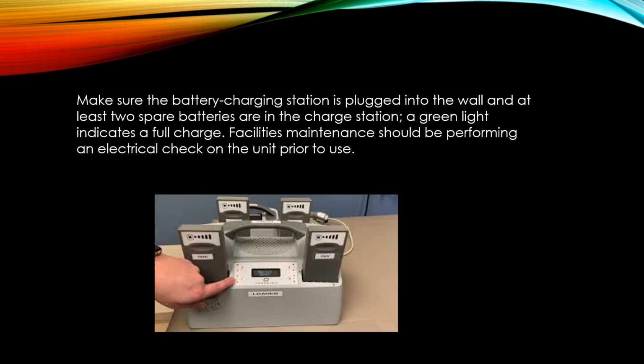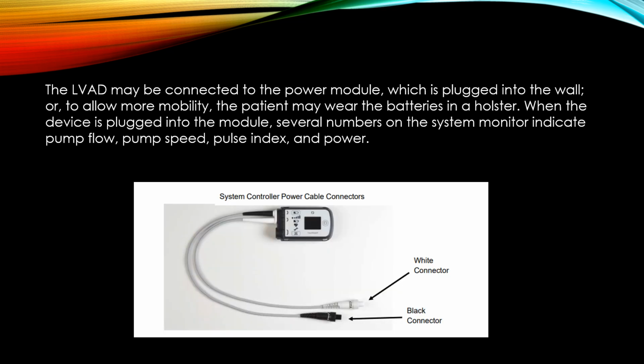Make sure the battery charging station is plugged into the wall, and they should have at least 2 spare batteries in the charging station. A green light indicates a full charge. Facilities maintenance should be performing an electrical check on the unit prior to use. The LVAD may be connected to the power module, which is plugged into the wall, or to allow more mobility, the patient may wear the batteries in a holster. You'll find that most patients will wear the holster during the day, and at night they'll be plugged into their wall charger. When the device is plugged into the module, several numbers on the system monitor indicate pump flow, pump speed, pulse index, and power.